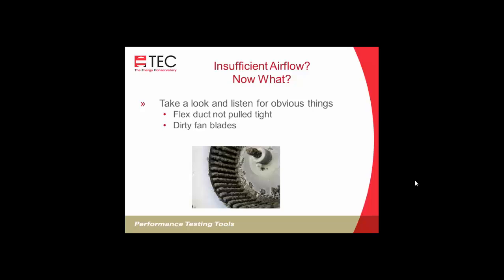Dirty fan blades, certainly over time, they get caked up with dust, and they just can't move enough airflow. So sometimes you have to pull that wheel, pull a motor, and take those into a wash tub or power wash them or something to scrub them, get those fan blades cleaned off. It's amazing what you'll find when you look.